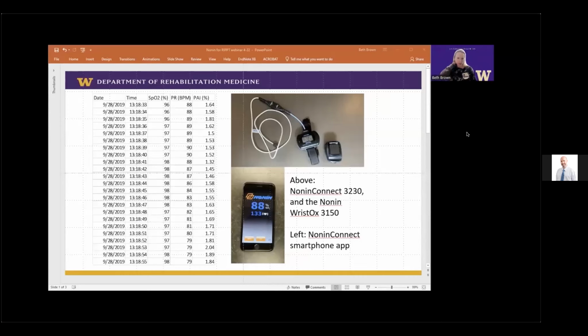At present, there are really only two choices available for the measurement of SpO2 during home or community-based exercise when an individual isn't at rest, and that is the fingertip sensors or the forehead sensors. A system that includes a forehead sensor is pretty common in the hospital and clinical exercise testing setting because it's less sensitive to motion artifact and it has the most accuracy when you compare it to arterial blood gases.